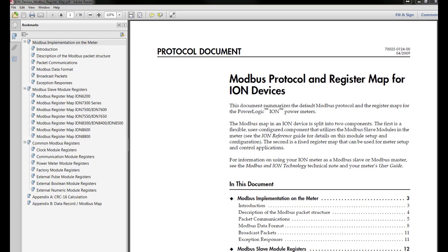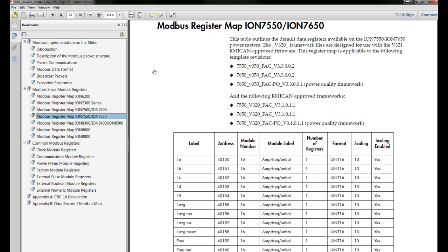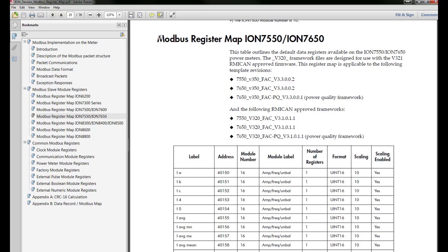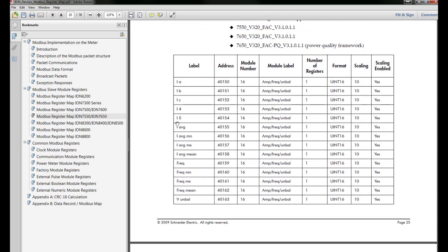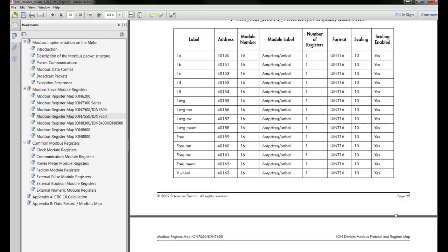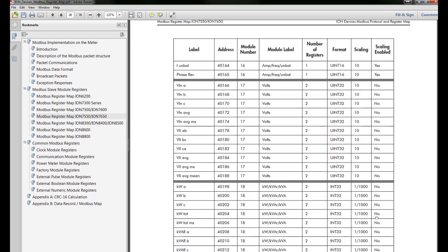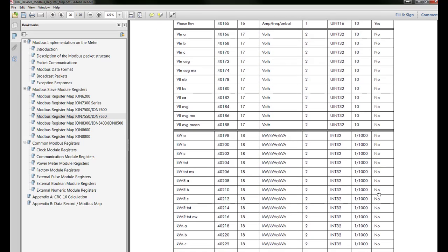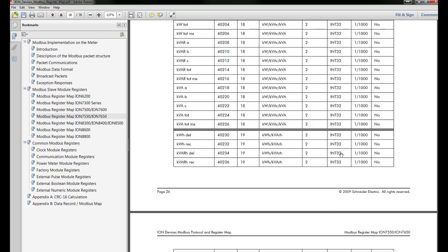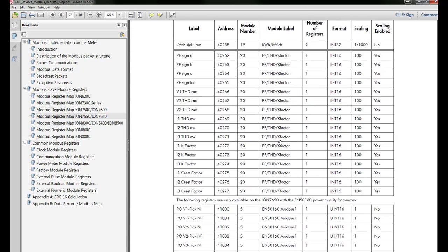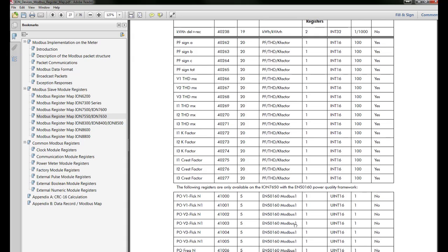Generally, when we need to read values from a Modbus device, the first task is looking for the Modbus map of the device. In this case, we have downloaded the Modbus map of the ION7650 meter from the Schneider Electric website. But what happens when we need to read the meter harmonic values and we cannot find the registers? By default, as we can see, the harmonic values are not mapped, even though we know that the ION7650 can measure from the 1st to the 63rd individual harmonic values.